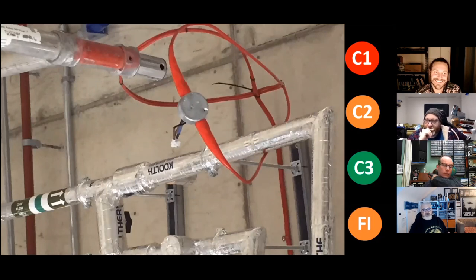What worries me, Dave, is the connector block configuration tells me that the only reason someone would have done that is not just to terminate it safely, but because they're testing it, because that might be part of a commissioned system. Yeah, so to me, this looks like the install, and maybe that is supposed to hang down on a suspended ceiling. Yes, and that's why it's hanging there. Obviously, it's not fixed to the ceiling or anything. So this looks like an installation stage, not commissioning.